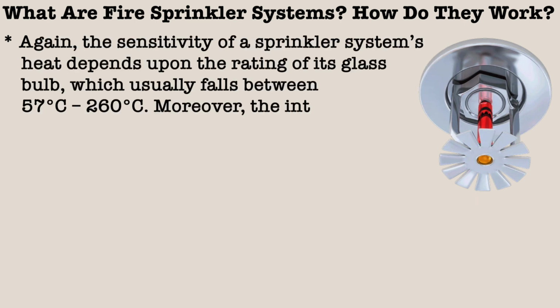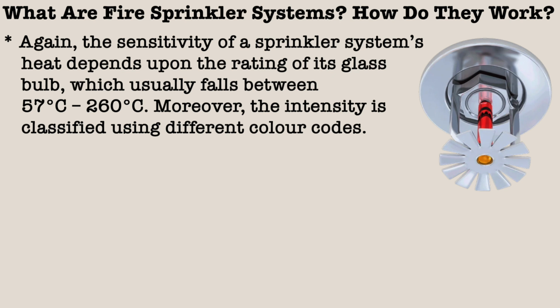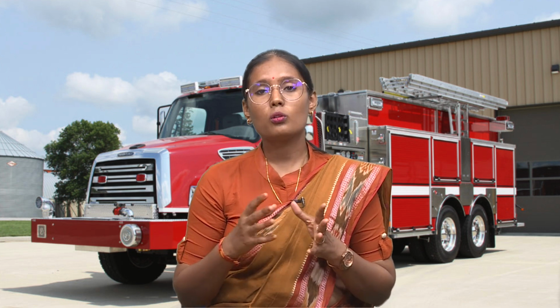The sensitivity of a fire sprinkler system's heat depends on the rating of its glass bulb, usually falling between 57 degrees Celsius to 260 degrees Celsius. This sensitivity is classified using different color codes. Further, the design of the sprinkler system is determined using the hazard classification of the building occupancy.